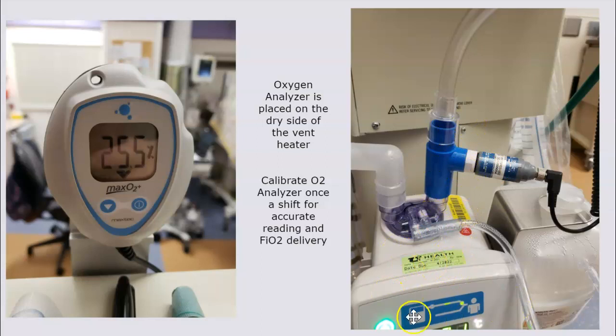So you can see we have a Concha heater here with our little box of water feeding in. This is the dry air gas line going in, and then we have our analyzer right here. You typically want to analyze this about every shift just to make sure that we have accurate readings of FiO2. And then it comes up to your analyzer to make sure that we're giving appropriate oxygen titration.